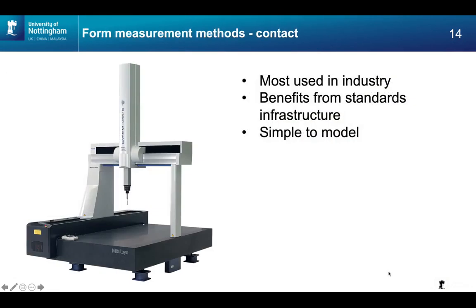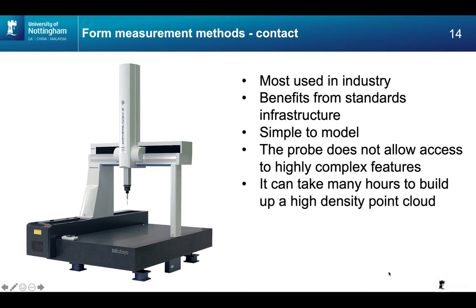So speaking first of form or coordinate metrology, the most used instrument out in industry at the moment is the contact coordinate measuring machine. And this, of course, benefits because it's been around for a number of decades now. So it has the benefit of a fully developed standards infrastructure for verification, I should say, not necessarily for calibration, although there are standards available on uncertainty as well, which we'll talk about. It's very simple to model how a mechanical probe contacts the surface. Just model it as a sphere. You might have to consider some contact mechanics, but typically it's much simpler to model than an optical system.